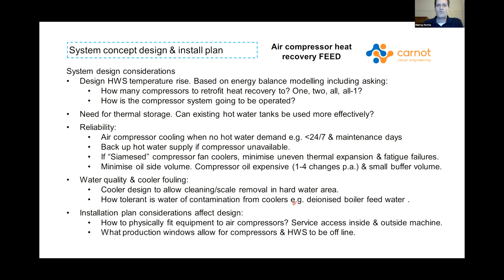How tolerant is the water that you're heating from having extra heat added to it? So I had a customer where the new compressors have been installed, 400 kilowatts of compressed air. They've got a big high pressure steam system, which was generating power before actually going out to the plant to provide process heat. And the customer said, no, I don't want water added to my boiler feed water because it'll overheat my feed water treatment system. He had big deionization tanks. And if we were to go in after the DI system, it would potentially recontaminate the water.